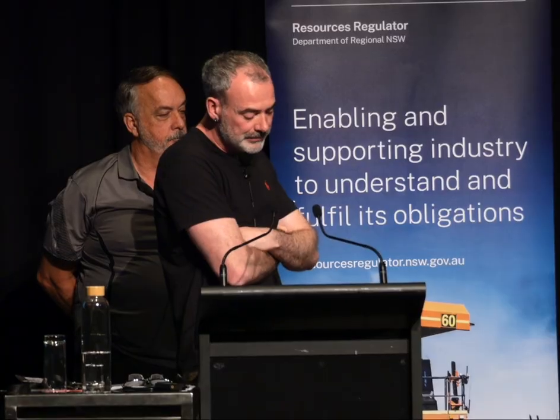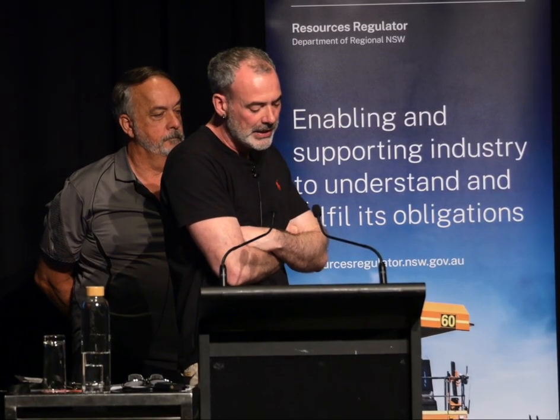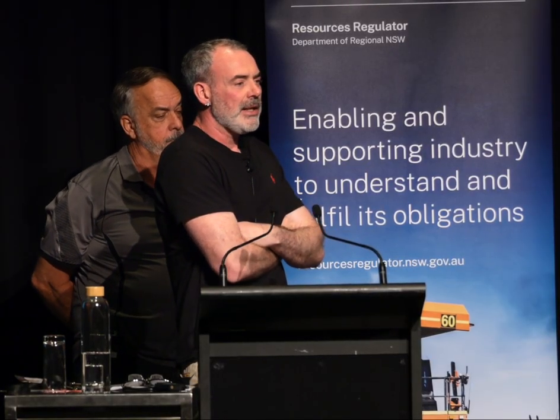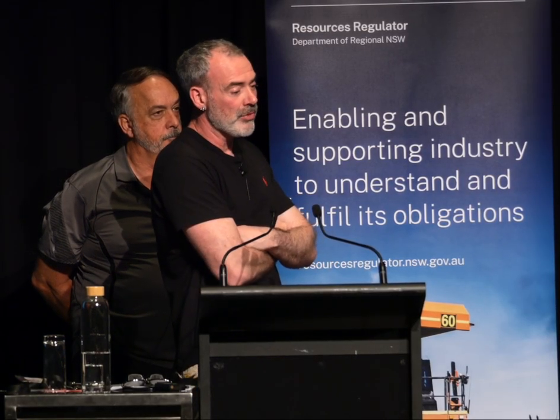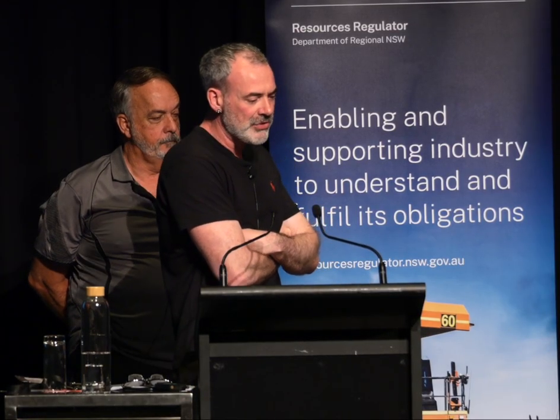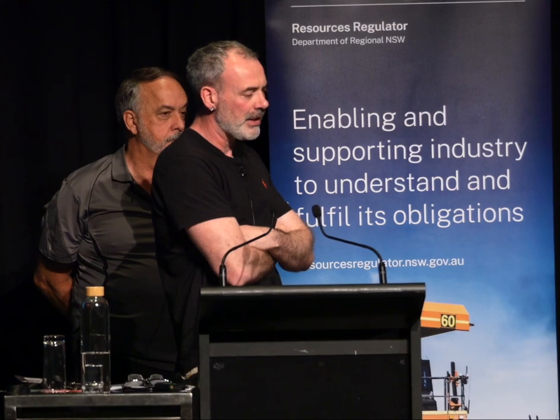So what we definitely don't advise is use of natural ester in free-breathing transformers, with or without a silica gel breather. For both natural ester and mineral oil, we want to avoid oxidation of the fluid or the oil. We know that synthetic ester, which we manufacture, is more oxidation resistant, but we advise use of a sealed system for a synthetic ester as well, because synthetic ester in a free-breathing transformer is going to have high oxygen levels. Under certain circumstances, this will lead to oxidation of the solid insulation, which is distinct from oxidation of the liquid insulation. Oxidation of the solid insulation can degrade the paper and reduce the life of the paper and therefore the asset. And also with synthetic, as I mentioned, ingress of moisture can lead to hydrolysis of the fluid, which produces a lower molecular weight acid than with natural ester, and that can also degrade the paper.